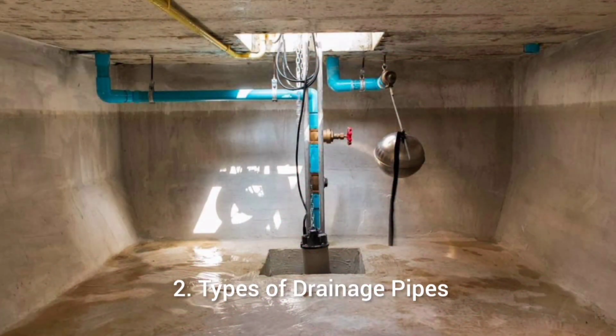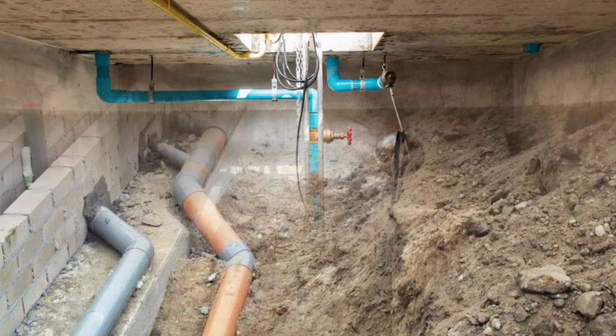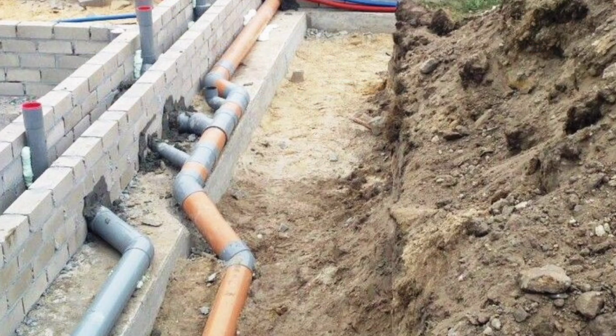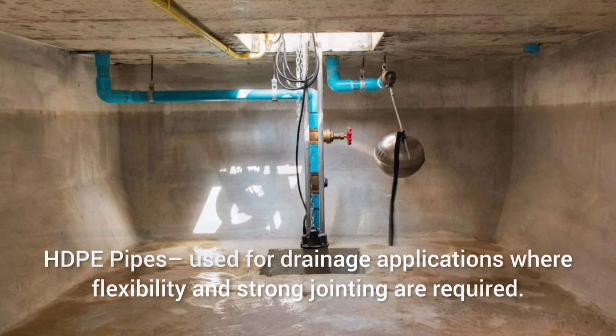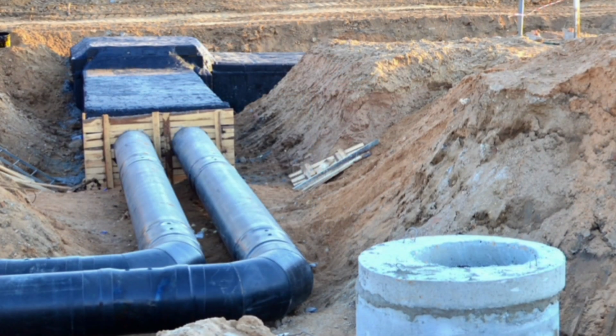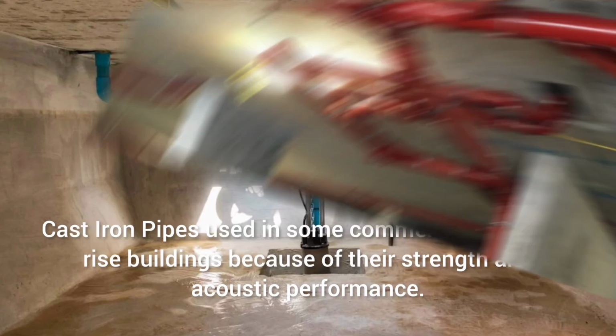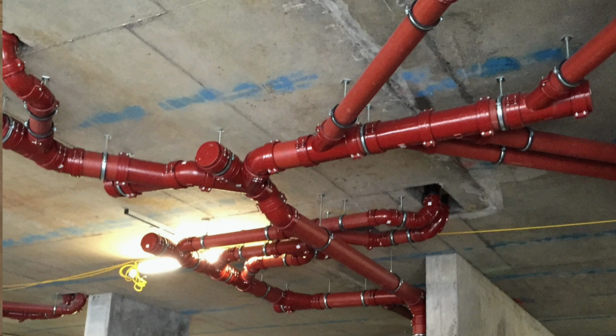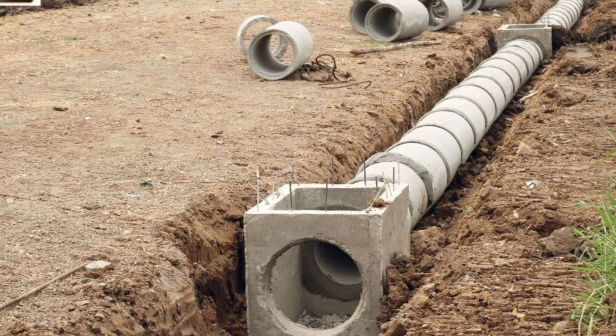2. Types of drainage pipes. Common drainage pipes used in buildings include UPVC pipes commonly used for soil, waste, and rainwater drainage. HDPE pipes used for drainage applications where flexibility and strong jointing are required. Cast iron pipes used in some commercial and high-rise buildings because of their strength and acoustic performance. Concrete pipes, generally used for external underground drainage networks. The selection of pipe material depends on the project design, building type, temperature, pressure, and local standards.